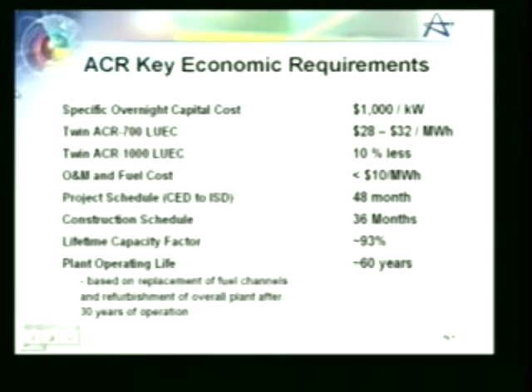Here are some of the key economic requirements. On capital costs, we're trying to make sure the plant can be built at $1,000 per kilowatt. So for a 2-unit, 700 megawatt plant, that would be $1.4 billion. As far as the LUEC, we're looking at $28 to $32 per megawatt hour. On O&M and fuel costs, less than $10 per megawatt hour.